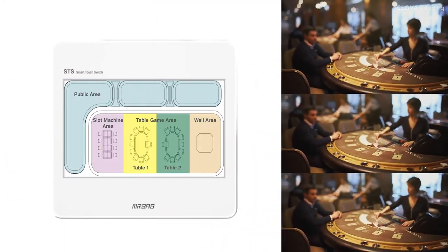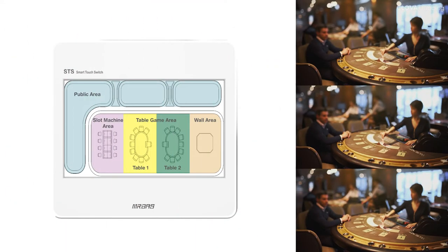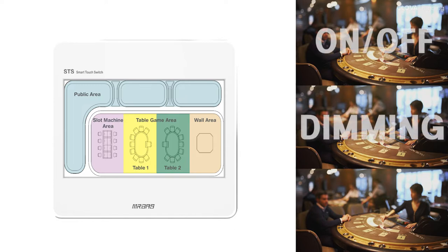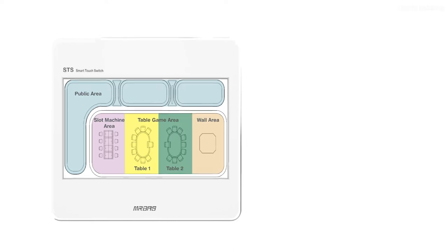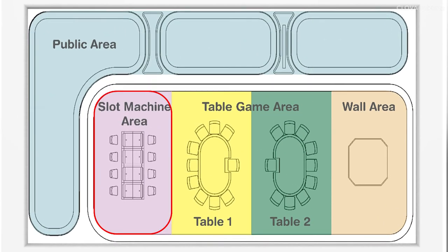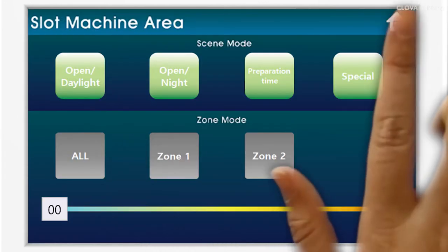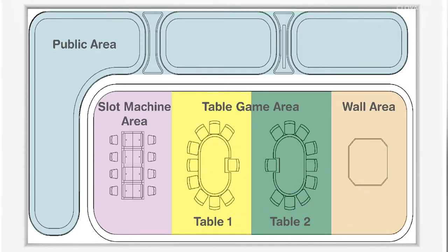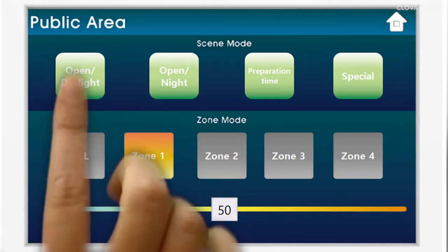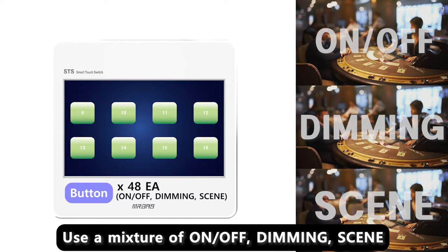Each area within the facility is controlled by the operator directly by a smart touch switch, allowing on and off, dimming, and scene presentation to be controlled on site. Using the smart touch switch's go-to-page function, you can select the area you want and enter the area control screen for convenient lighting control. Each area supports up to 48 buttons on the switch, which can be used with a mix of on and off, dimming, and scenes.